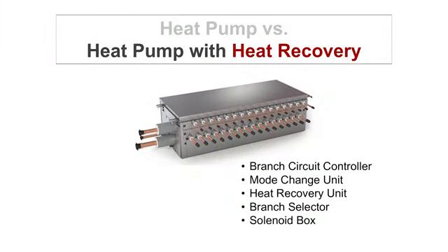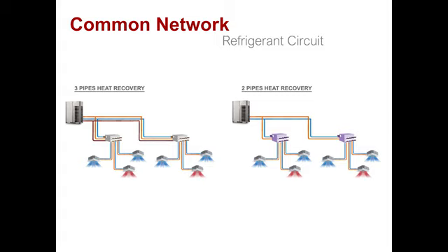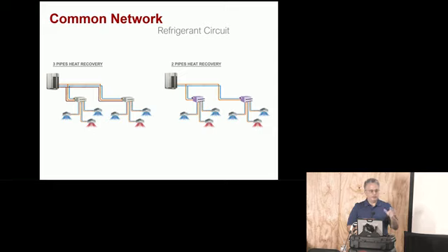So this is an illustration, and these are the different names that different manufacturers use, but it's the same thing. They are constructed and designed differently, but essentially they perform the same work. And in this category of heat recovery, there are two different styles. You have a 3-pipe system, and then you have a 2-pipe system. So you could have 2-pipe heat recovery or 3-pipe heat recovery. And there's a lot of arguments, which one is better, what have you. It really depends on the job. There's arguments for both. Both work, generally speaking, fine if you go with the top names.